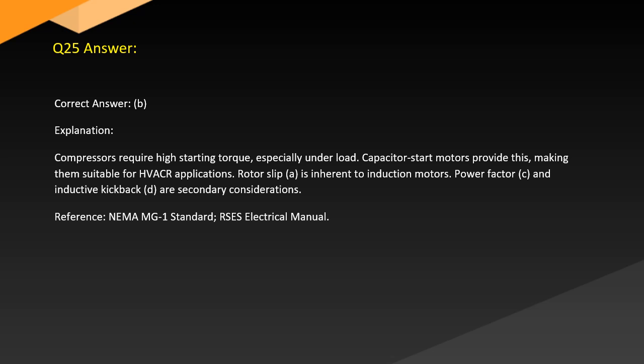Answer. Correct answer, B. Explanation. Compressors require high starting torque, especially under load. Capacitor-start motors provide this, making them suitable for HVACR applications. Rotor slip, A, is inherent to induction motors. Power factor, C, and inductive kickback, D, are secondary considerations. Reference: NEMA MG1 standard, RSES Electrical Manual.